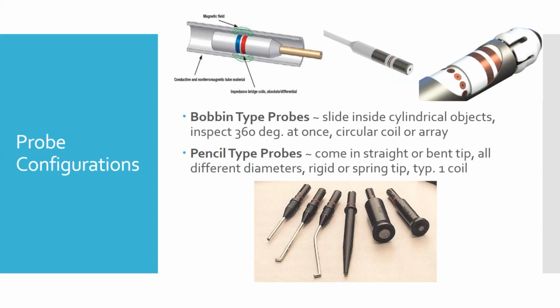Okay. And then pencil probes at the bottom, the four on the left here, have one tiny little coil typically at the tip. They fit into tight areas. They fit well in curved areas and that kind of thing. And they are good for odd geometry parts. You can see they come in different shapes, whether it's a straight probe, a 90-degree probe, or a bent probe. This one right here is a precision probe. The three on the left, you tend to hold further up near the top. That's your grip. This one right here, coated all the way down to the very fine tip, is designed to be held like a pen, where you can manipulate it very precisely across your part.